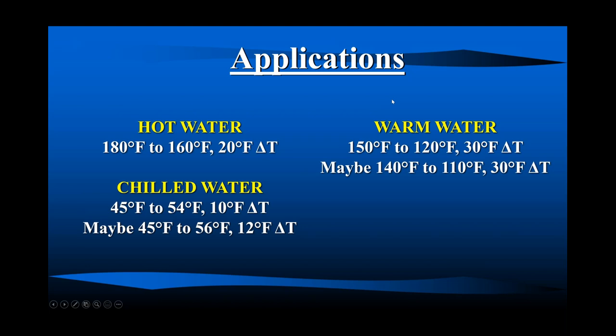But we have to, even that's not the same, right? Maybe we have to go 140 to 110, stay at 30 degree delta T, right? We don't know what's going to happen with our gas condensing boilers. I may know they're changing everything from gas to something else. Air to water heat pumps are the likely choice, and that's only going to go up to 140. So that may be our new water temperature system we have to use.